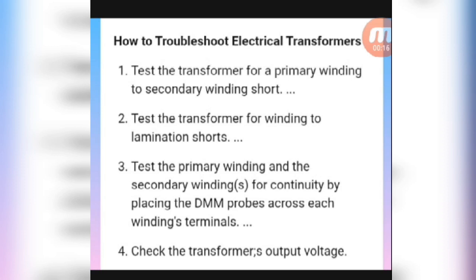Test the transformer for a primary winding to secondary winding short test. Test the transformer for a winding to the lamination short test. Test the primary winding and the secondary windings for continuity by placing the DMM probes across each winding terminals.